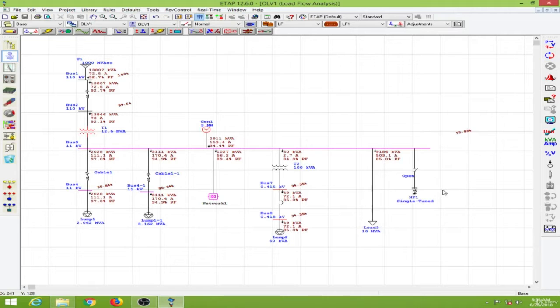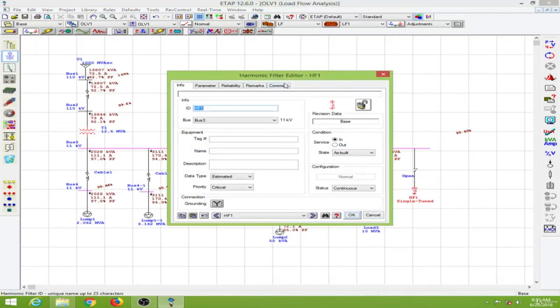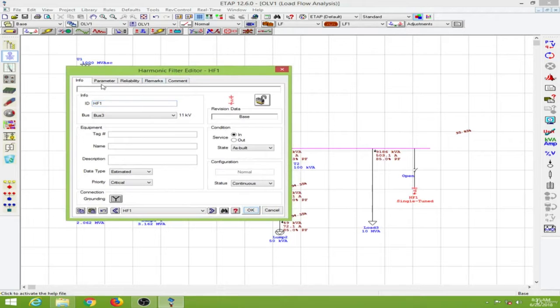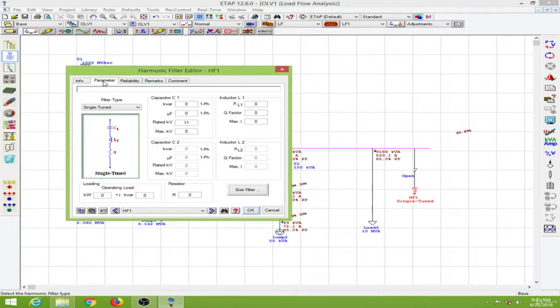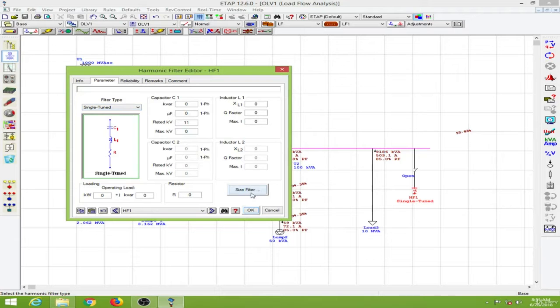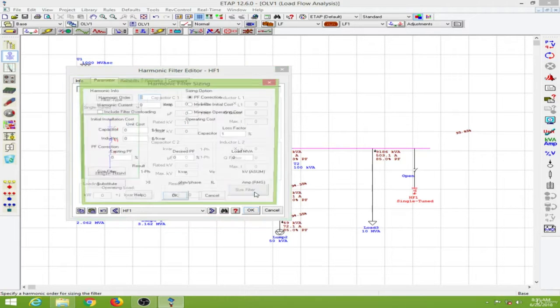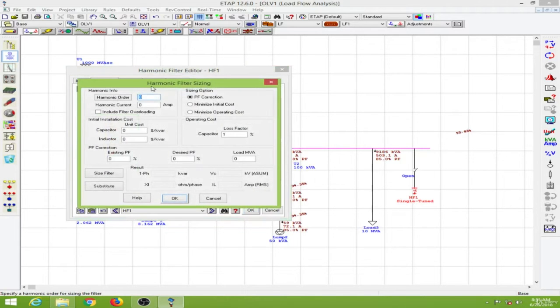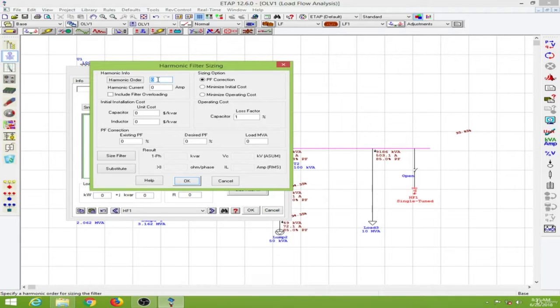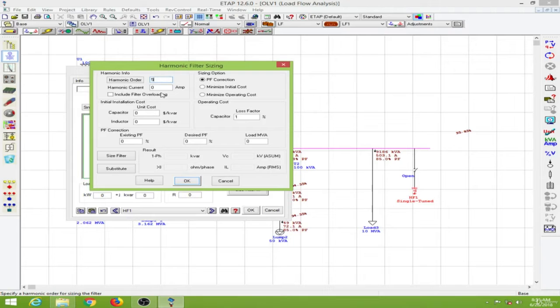Now double clicking on the harmonic filter brings up the filter editor window. Going to the parameters, the filter type I'm using will be the single tuned filter type. I will go to the size filter option. The harmonic order I want to eliminate is the fifth order harmonic, so I will put in the fifth order.